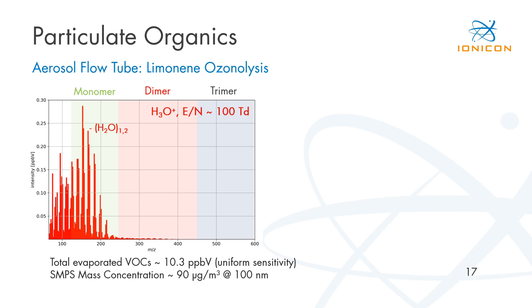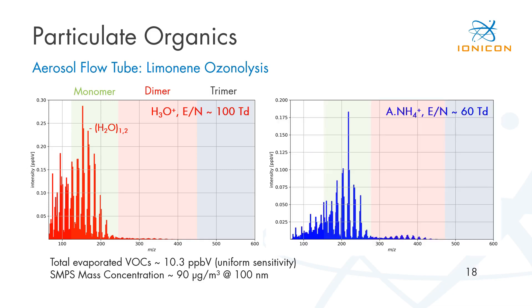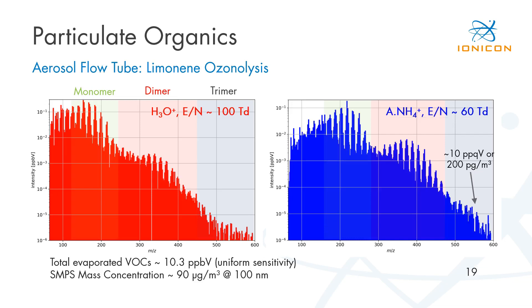For more detailed insight into the mass spectrum and chemical composition, we can switch to soft ammonium adduct ionization mode. We reduce the E/N to 60 Td to produce stable adduct clusters with ammonia. Now the monomer fraction is even better visible. We still have some interferences from one to five percent proton transfer reactions, but the dimer fraction of the evaporated aerosol is significantly more pronounced. Looking at the mass spectrum in more detail, we can even see a trimer fraction with mass concentrations of less than 200 picograms per cubic meter, or 10 parts per quadrillion. This mass spectrum is only an average of two to three minutes, demonstrating the very high sensitivity of this Fusion PTR-TOF instrument.